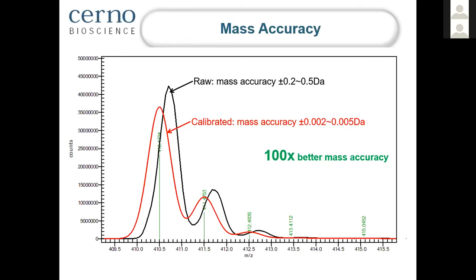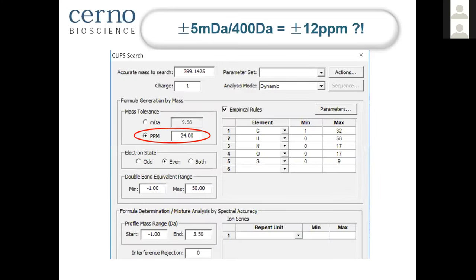The question is, would 100 times more mass accuracy be sufficient to perform elemental composition determination? Well, if we convert that, plus or minus 5 millidalton, the third decimal point kind of mass error, at 400 m/z, that translates to about 12.5 ppm mass error. And that mass error is one standard deviation. So when we try to determine an unknown, we want to enlarge that by at least a factor of two, or even three. So let's say we go to two sigma, two times the standard error. When we search for possible unknown elemental compositions, we want to search within plus or minus 24 ppm.